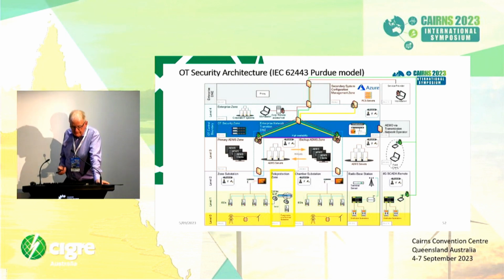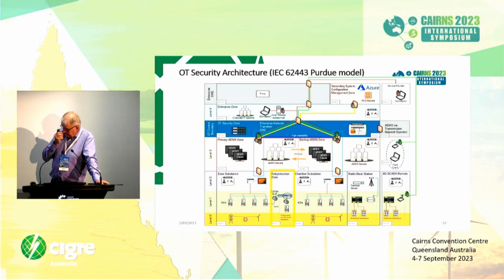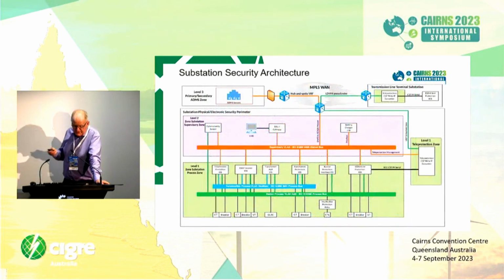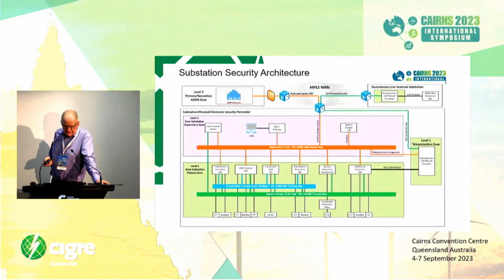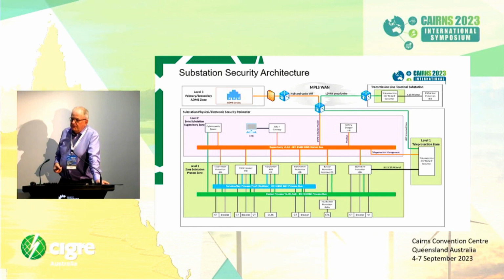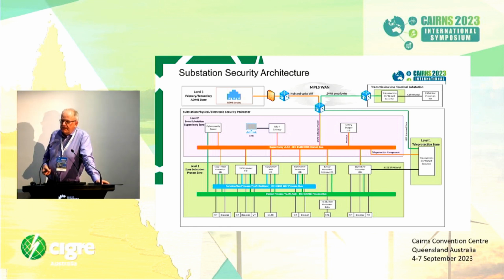So importantly, we consider teleprotection to be separate from our zone substation security zones. And that's for one very good reason, which I'll get to on the next slide. The risk with teleprotection is that it offers a very low level, layer 2 point-to-point IP service between substations. So it's very important that we're not bridging our networks between substations. Just understanding where the demarcation points are, the different security zones within your substation, is very important.